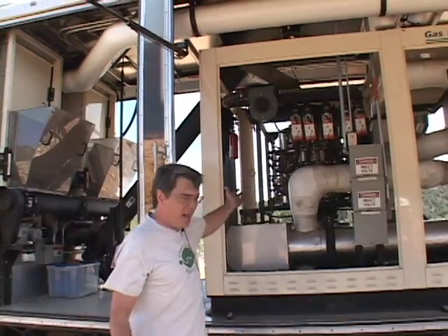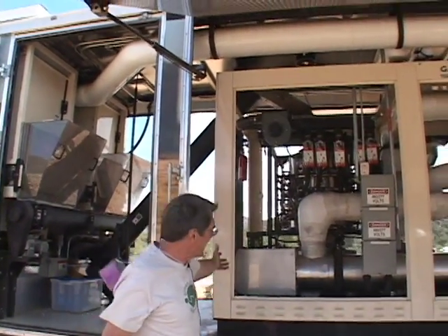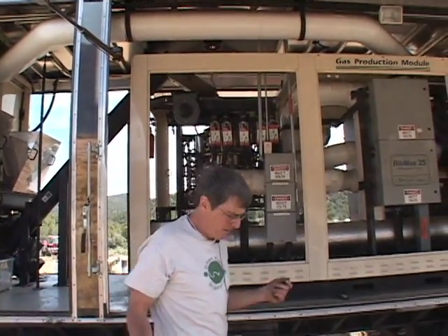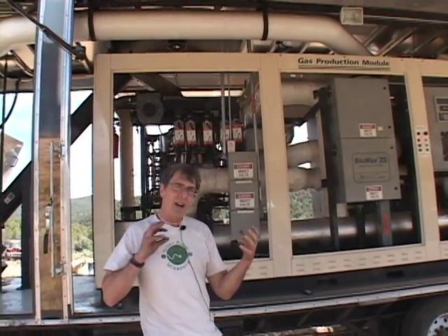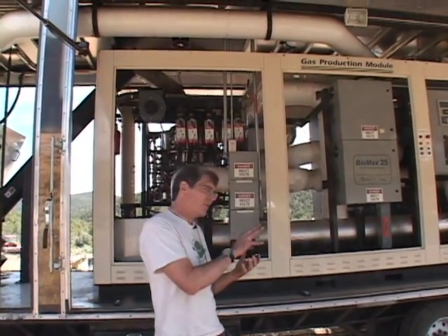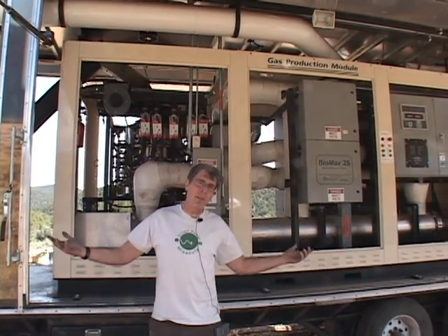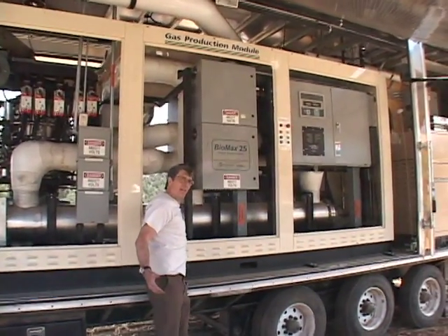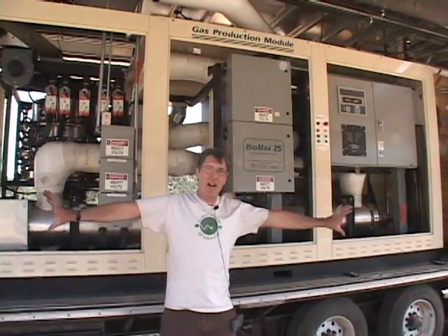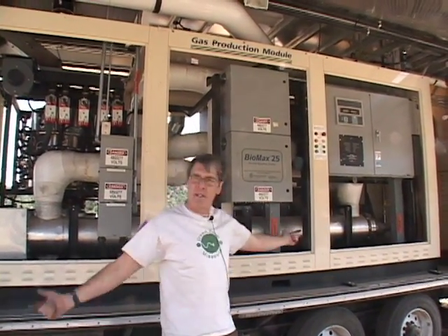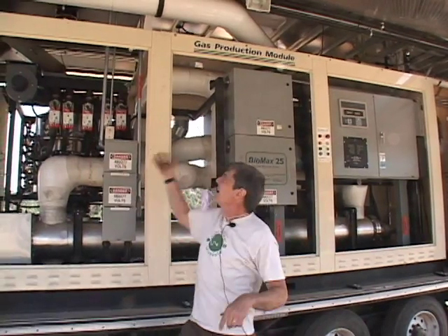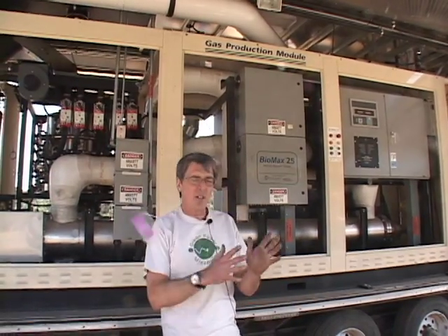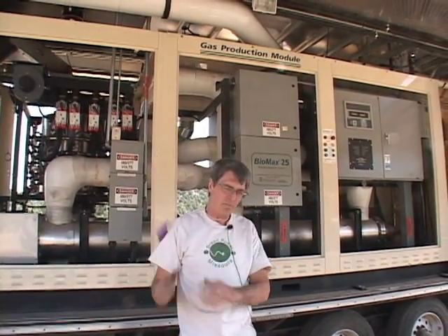From the other side, I mentioned we had the gasifier. The hot gas comes out, it goes through this heat exchanger. This heat exchanger is just a tube and shell. The hot gas and the entrained char goes through the tube side. We just use ambient air as a coolant. The ambient air comes in the middle of the heat exchanger and is pushed out to either end. At either end, the hot air is recovered and travels overhead back into the bin area, where I can choose which bin to dry it with.